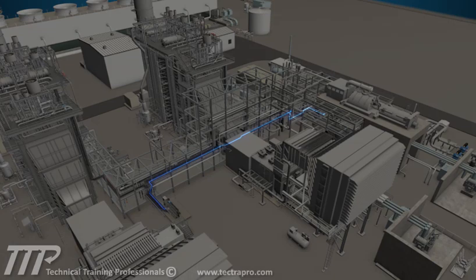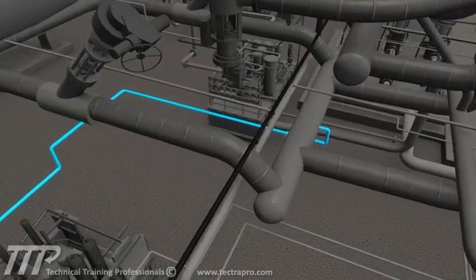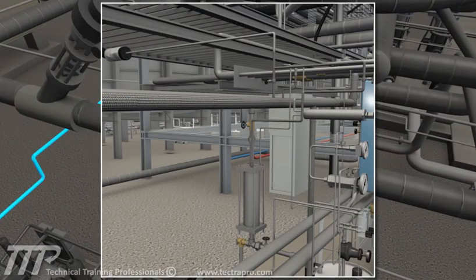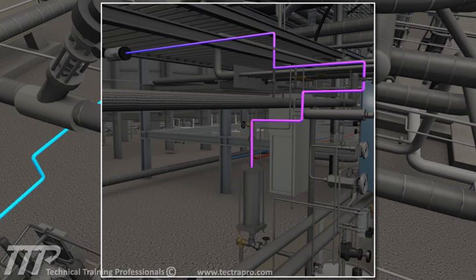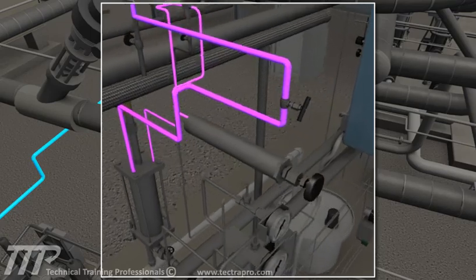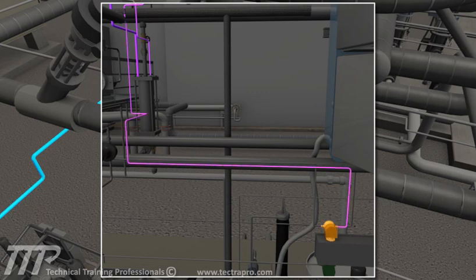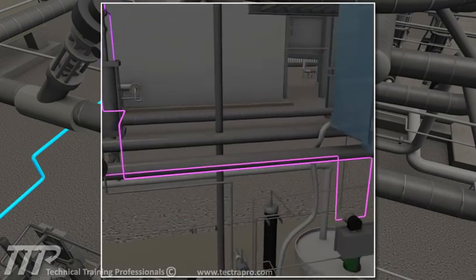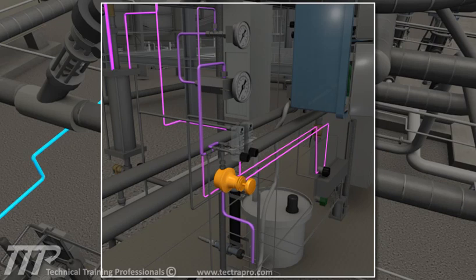Sample point 11 is the hot reheat steam line, upstream of the intermediate section of the steam turbine. At the sample panel, the steam is condensed by a higher capacity cooler due to its much higher temperature. Flow is adjusted by a flow control valve. A temperature switch, located downstream of the flow control valve, will close an inline solenoid valve should the temperature of the sample exceed the temperature switch setting. This protects the sampling equipment and operating personnel from exposure to high temperature fluids. A back pressure regulating valve is installed to provide stabilized flow throughout the sample flow path and a minimal flow to the sample sink to allow for grab samples.